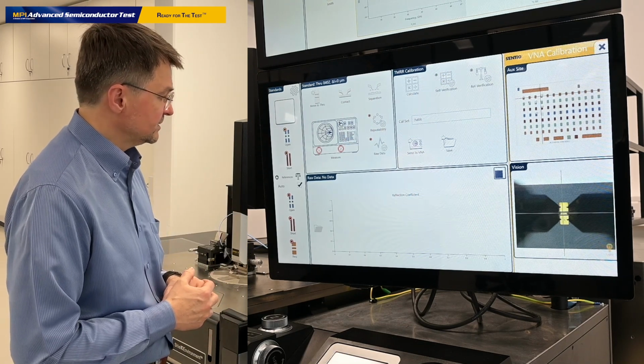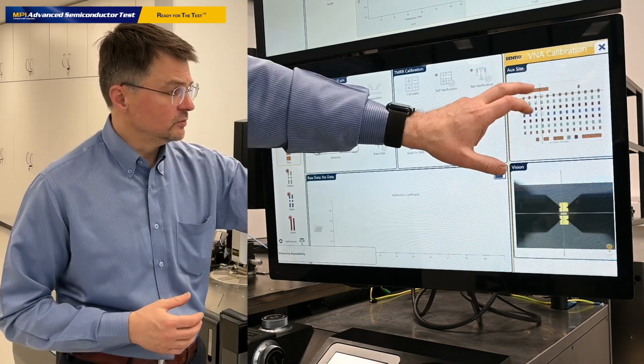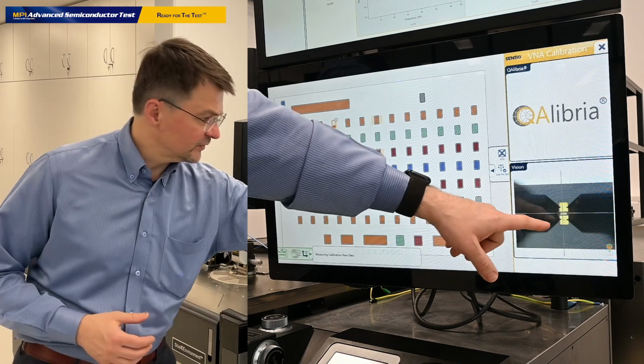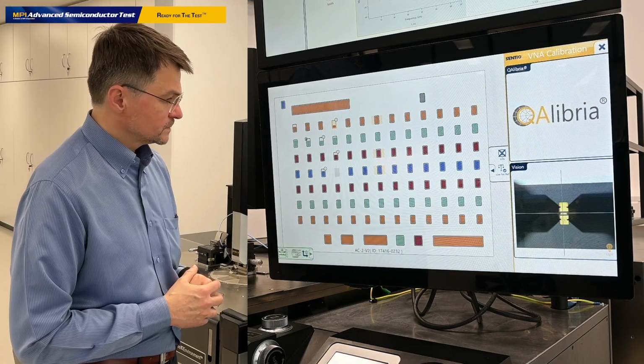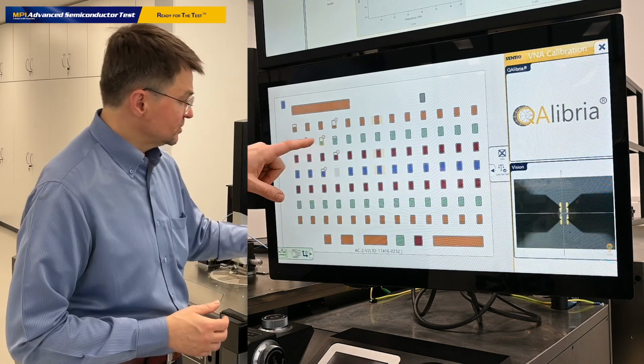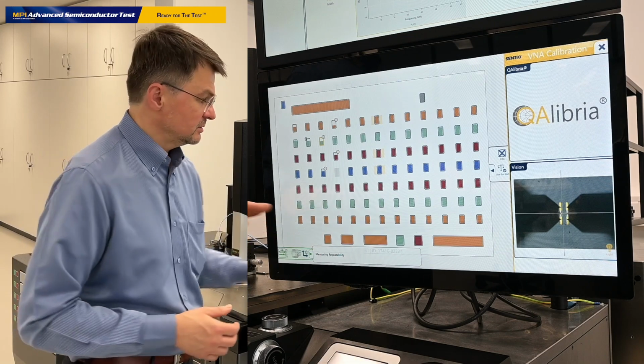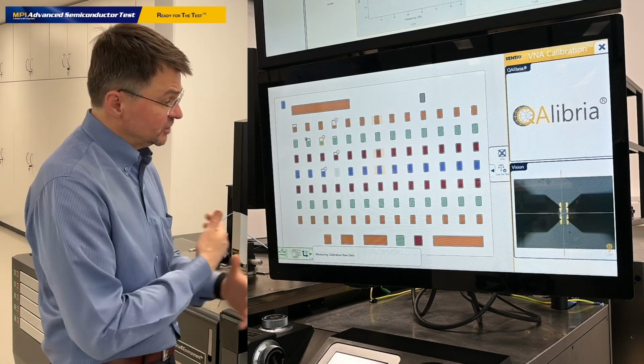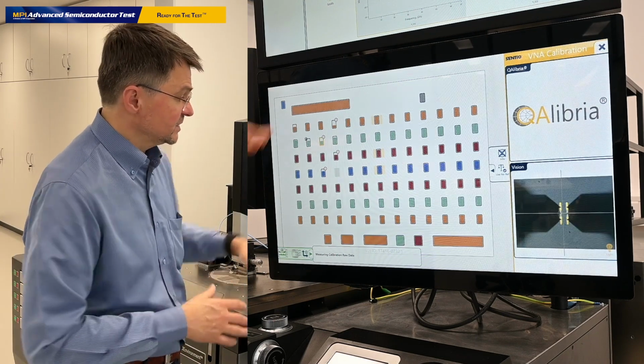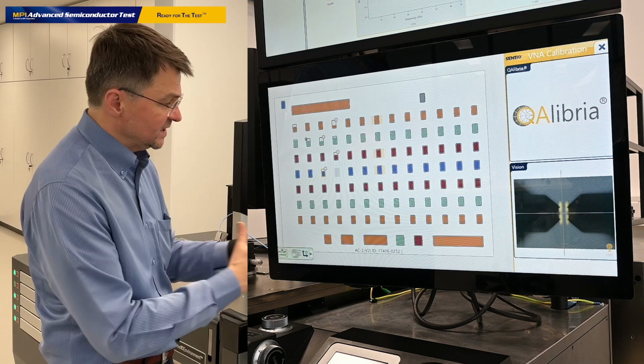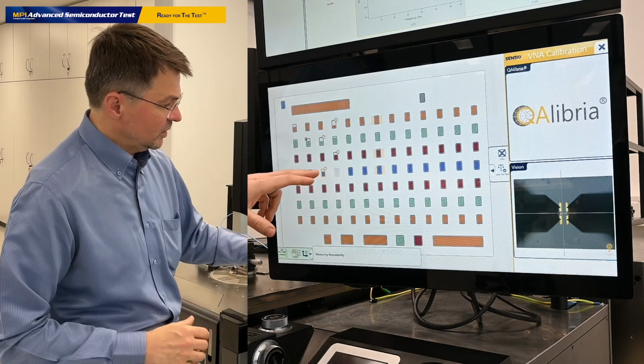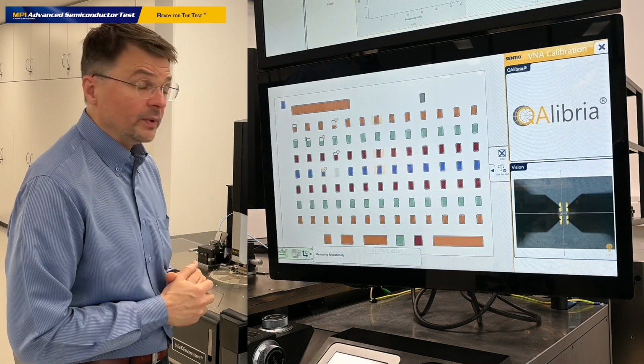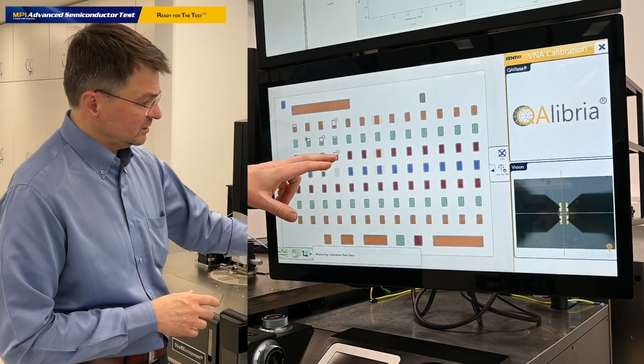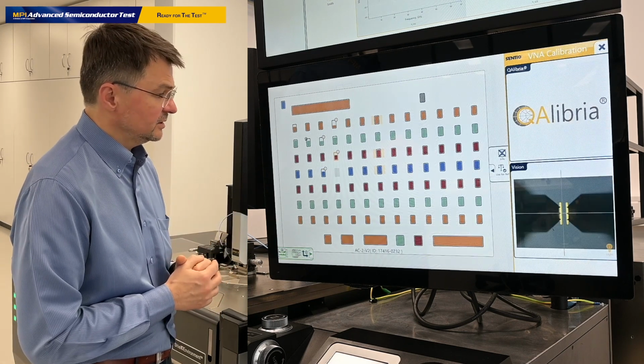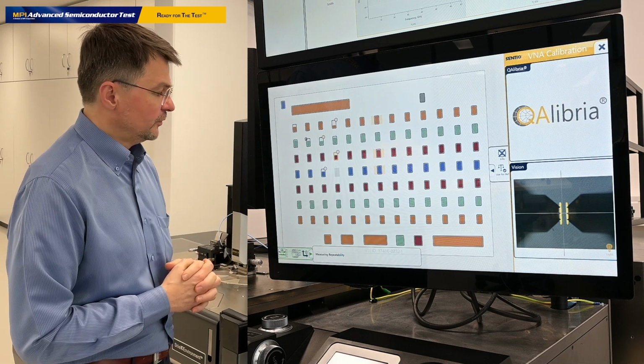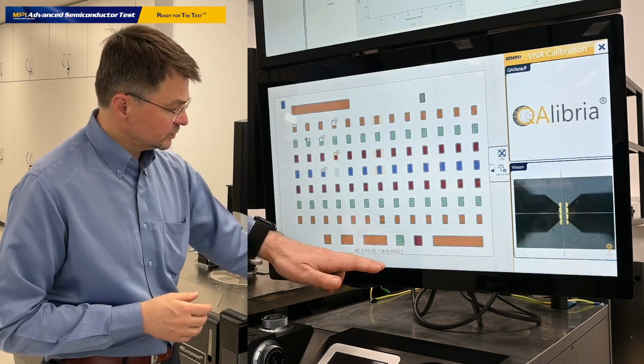We trigger the calibration process. We measure calibration standards at first, so we move to our calibration standard, which is our through standard. We are somewhere here right now. We collect measurement data. Then we move to the load standard. We are over this load standard. As you see, we can live track the location and the calibration progress, not only through the QAlibria graphical user interface, but also through any other parts of Sentio related to the calibration process. Now we are over the map. So we are over this open element, and the last will be the short element, which is here. You see the red circle marking means that this is an element that will be used for the calibration process. And the execution process is also shown here.